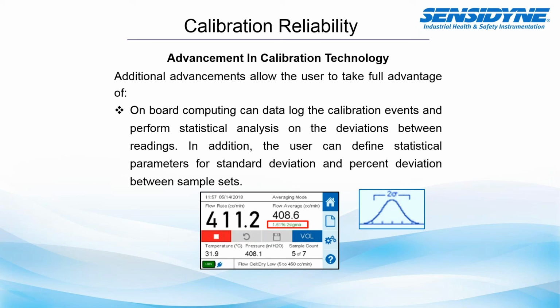So onboard computing can also data log the calibration events and perform statistical analysis on the deviations between readings. What do I mean by this? In the illustration shown below, you see a red box around a 2 sigma, which is your standard deviation. This really shows that each one of my individual samples within that 7-count sample set has a deviation or precision about it. You really want that tight shot group.